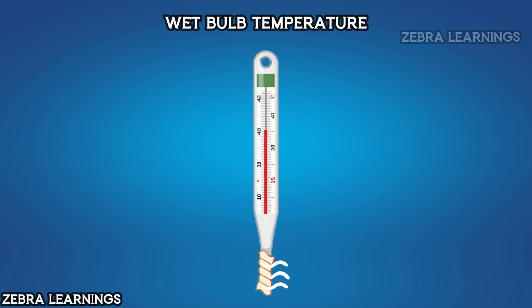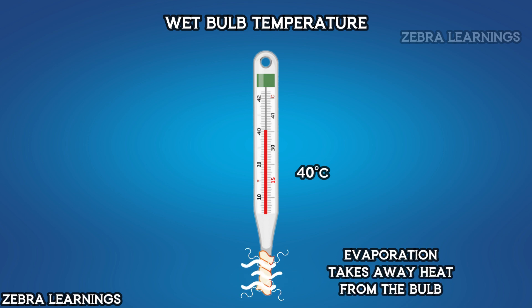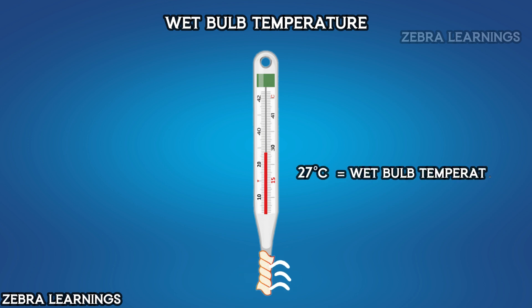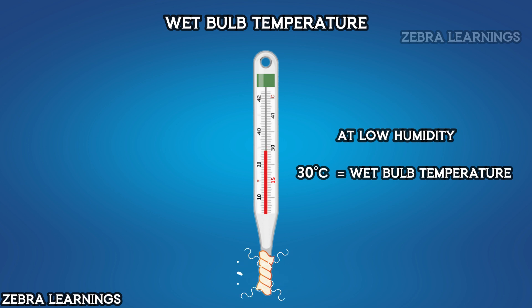The mercury will expand to the same temperature as the air. However, when water evaporates, it takes away some heat, so it removes some heat from the bulb. The removal of heat causes the bulb's temperature to decrease, and this temperature reading is the wet bulb temperature. When humidity is high, less water evaporates, so less heat is removed from the bulb, resulting in a higher wet bulb temperature. When humidity is low, more water evaporates, so more heat is removed from the bulb, resulting in a lower wet bulb temperature.